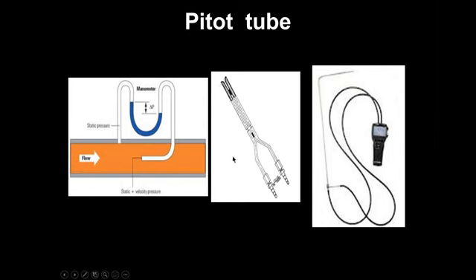Basically, what a pitot tube is doing is measuring the static pressure and total pressure. I don't have to explain probably this to you. There's static pressure and total pressure, that is static plus velocity pressure. So for that, each pitot tube will have 2 sets of tubes. Like this, this is for measuring the static and this is for measuring the total pressure. Here again, of these 2 tubes, one will be along the direction of flow, the other will be against the direction of flow. So this will measure total pressure, and this, which is on the opposite side of the flow, will measure the static pressure, because the velocity is not going to get impinged on that. But here it will get impinged, it becomes 0. So here it will get converted, and total pressure will get measured.